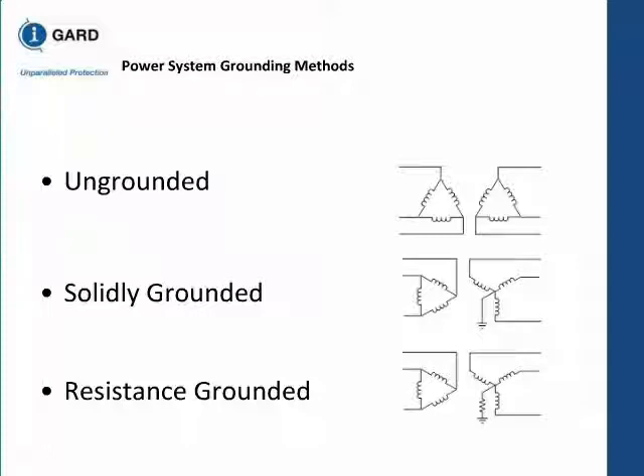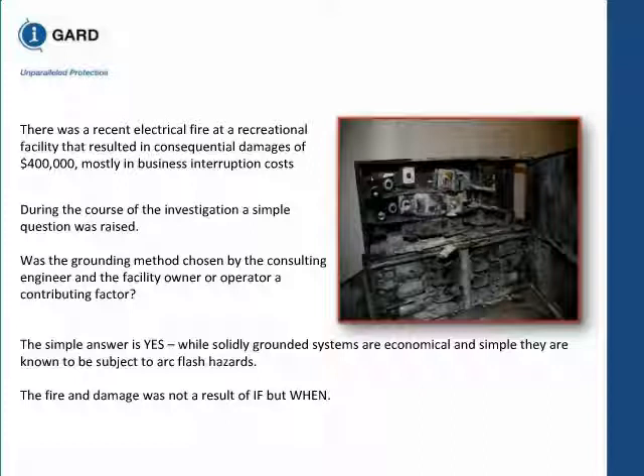This was a recent electrical fire on a solid grounded system, and you can see the losses were 400,000. During the investigation and legal cases, the question was asked: was the grounding method chosen by the consulting engineer and facility owner a contributing factor? The answer was yes. If you have a solid grounded system, it's a cost saving. They're simple, but they create more flash hazard. Anytime you see black deposits on this equipment, as you can see on your screen, that means it was an arcing fault. Arcing faults are preventable. If it's a solid bolted fault, you would not see any deposits on the equipment. So anytime you go for an investigation, keep that in mind.